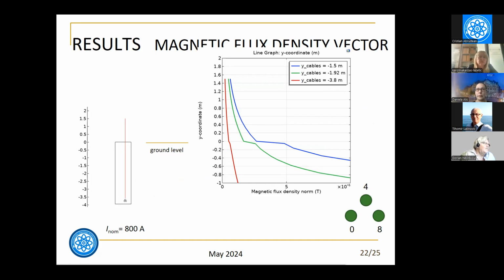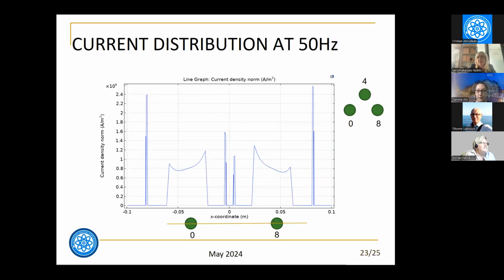And we have a similar graph for the trefoil configuration of cables. Here is the ground level, and we can compare the values as a function of the height, the depth of the cables in the soil. And the distribution of current density in the lower 2 cables in the center line, we can see the proximity effect, the additional effects from the cables being near one to the other, and these a little bit higher values are the induced current in these metallic layers from the conductor.